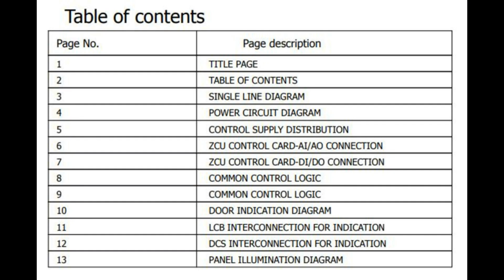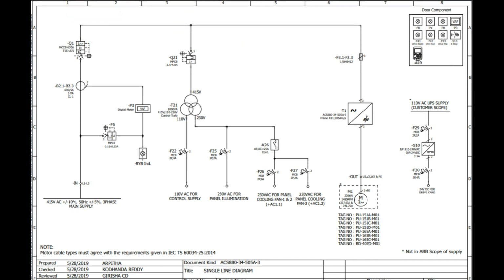We will start with page number 3, that is the single line diagram. From the left hand side bottommost you can see the main supply is given to the complete circuit, that is 415 volt plus minus 10% tolerance, 50 Hz frequency plus minus 5% tolerance, 3 phase. So this is the main input to the drive.